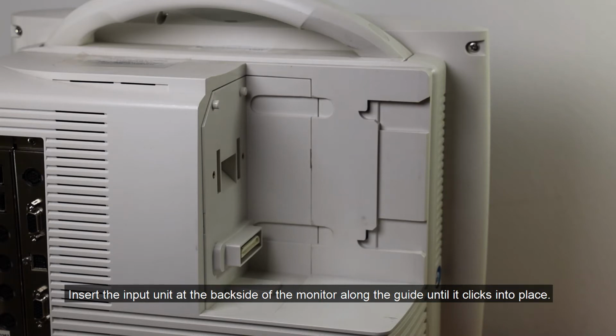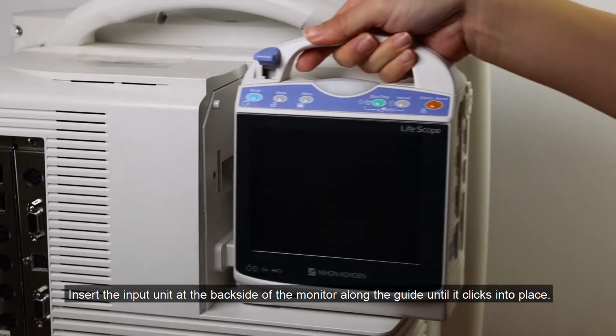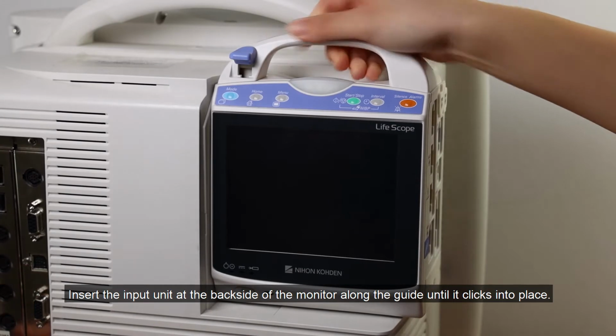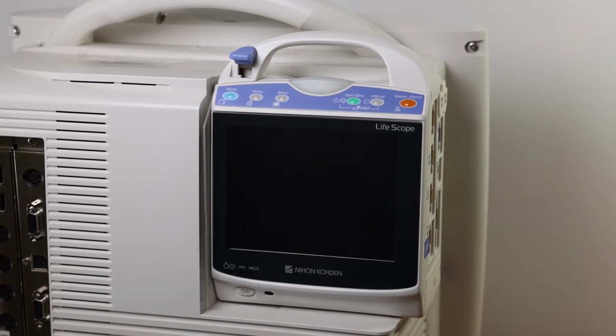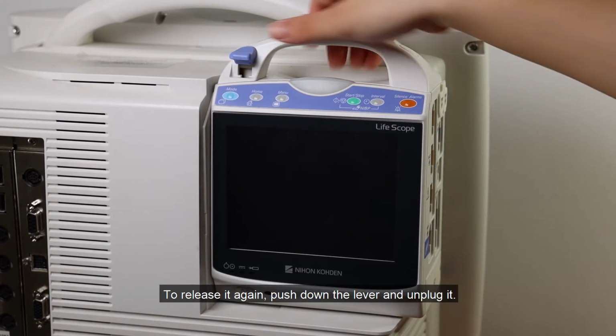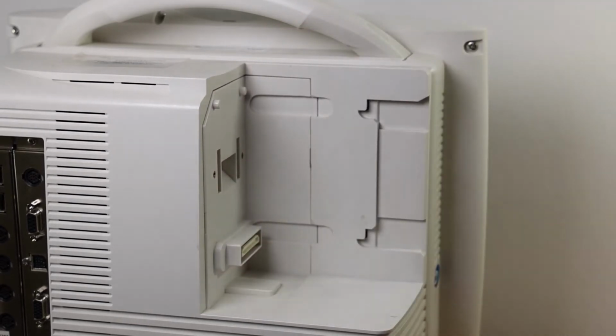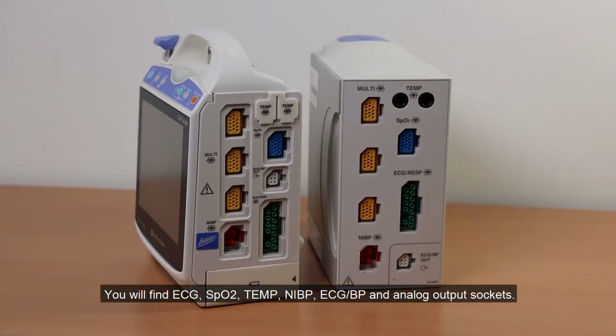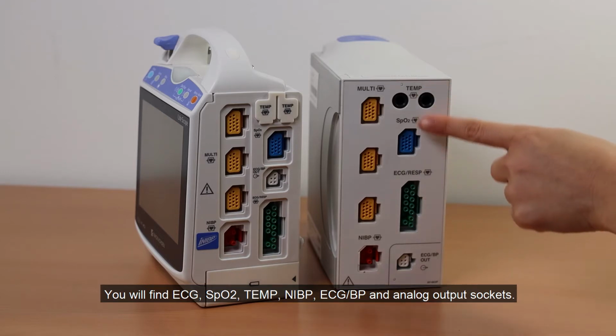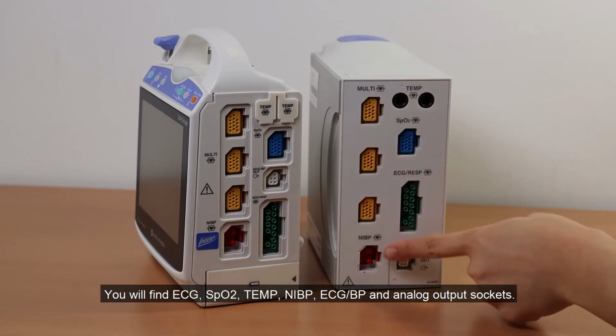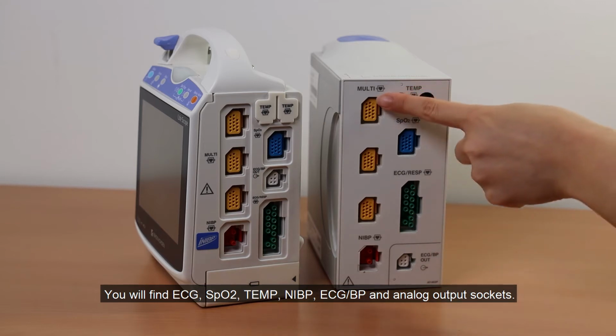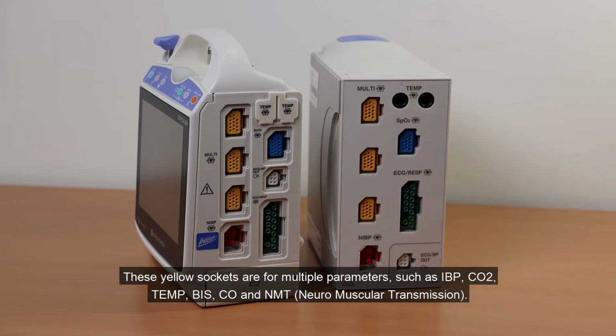Insert the input unit at the back side of the monitor along the guide until it clicks into place. To release it again, push down the lever and unplug it. You will find ECG, SpO2, temperature, NIBP, ECG BP, and analog output sockets. These yellow sockets are for multiple parameters such as IBP, CO2, temperature, BIS, CO, and NMT.